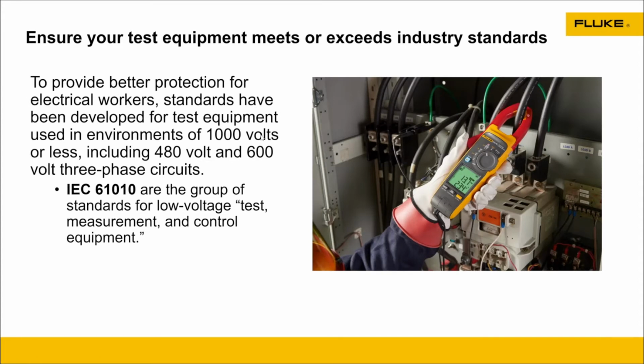So, part of manufacturing and part of knowing, because your meter is part of that extension of your PPE, is making sure that it was manufactured correctly. The IEC 61010 is a standard on low voltage test, measurement, and control equipment. This is basically meters and clamp meters, etc., that will measure under 1,000 volts. Once we get above 1,000 volts, that actually becomes medium voltage. So if you're working on 480, you're working on 600, say three-phase circuits, that's under that 1,000-volt range.